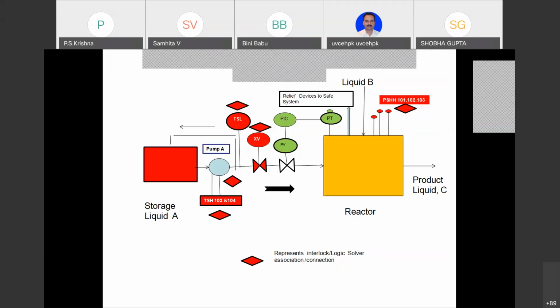And then they shut down the reactor. They did the nitrogen purging, everything, spending so many dollars, and then when they started again, they found this was a false trip or spurious trip. We don't want that. We want a real trip. Because this can fail, this can fail, this can fail, the 2 out of 3 voting system, you're going to see, is the best mode. So we wrapped up this plant and gave it to them, and they produced that stuff. And everyone was happy.